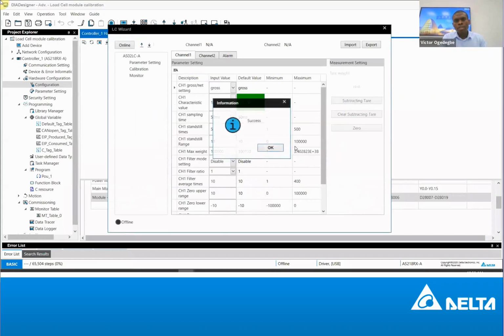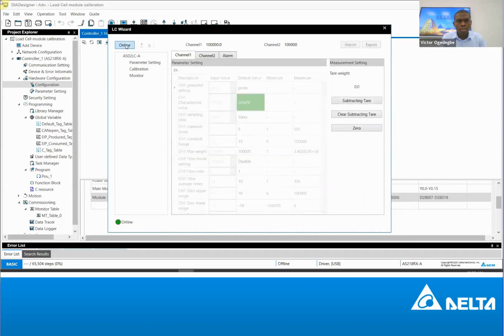If you double click on this, it opens up the load cell wizard for you. From this load cell wizard, you can configure what the control register does. That is what this load cell wizard also does. If I go online, you can see there is no value because I've not even configured the module. But we'll soon get there.